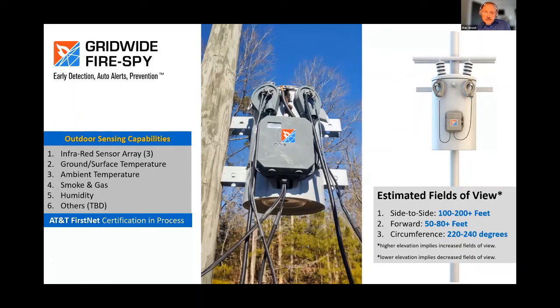I do want to mention the estimated fields of view. This has been developed through different testing on the angles upon which we have these infrared sensors deployed inside each device. But all transformers are not at the same height in the field—typically between 30 to 40 feet. So the higher up you go, inherently the larger the field of view or footprint we have with regard to seeing the ground and understanding, through infrared sensing, the temperature changes that may be occurring.